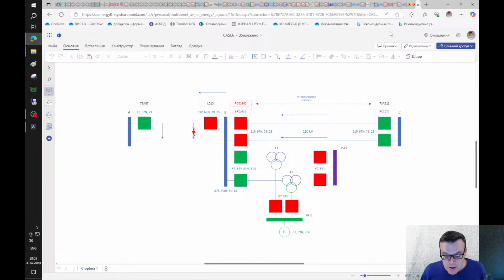Maybe I forgot something. What I want to describe is lessons learned. So first of all, sometimes voltage dependent overcurrent protection, like in this situation, can lead to a bigger clearing time, because we have automatic reclosing. During the war I see the same problems. So when some protection can't operate, or fails to operate, or was destroyed, the automatic reclosing from backup protection functions can lead to a longer clearing time. This is one point.